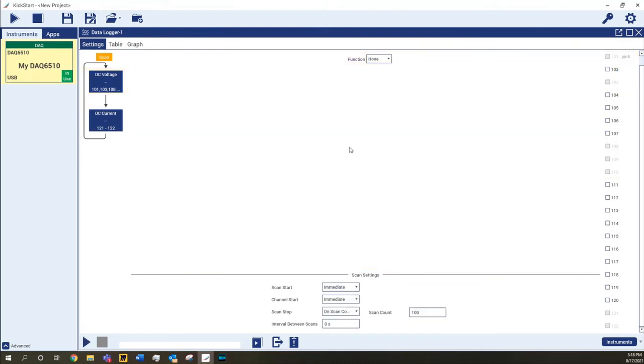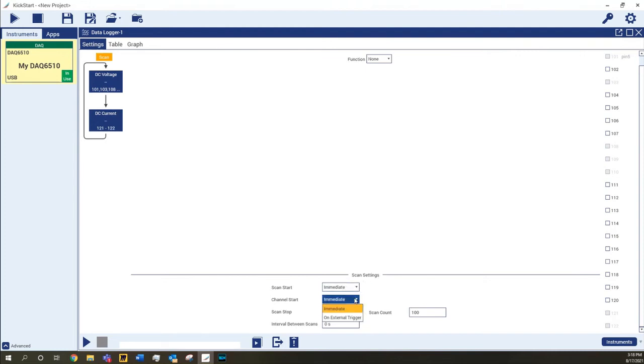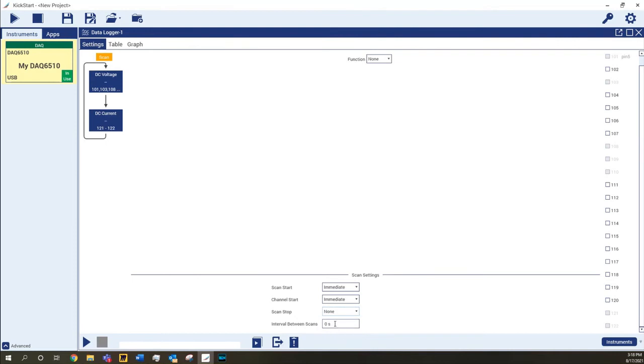At the bottom are the settings for the entire test. A data logging test is comprised of multiple scans, each scan taking measurements at each channel. You can configure how the scan is started and how the measurements on each channel are started. Configure a discrete number of scans to run, or set a time limit for your test and the scans will be repeated until the timer expires. Selecting None allows the scan to run indefinitely.